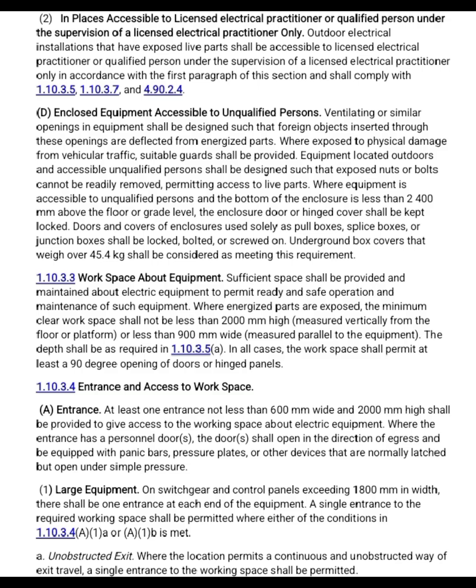D. Enclosed equipment accessible to unqualified persons. Ventilating or similar openings in the equipment shall be designed such that foreign objects inserted through these openings are deflected from energized parts. Where exposed to physical damage from vehicular traffic, suitable guards shall be provided. Equipment located outdoors and accessible to unqualified persons shall be designed such that exposed nuts or bolts cannot be readily removed, permitting access to live parts.